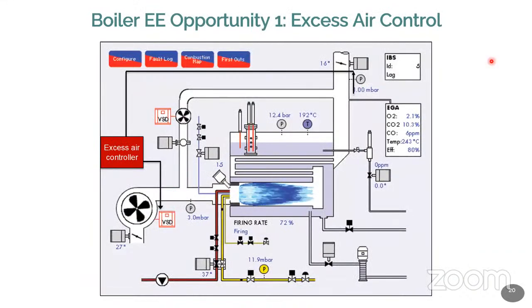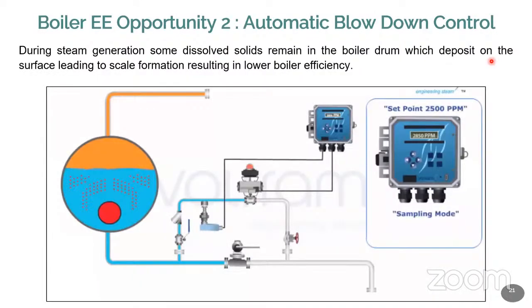Okay, so this will show the way in which the system is working, with monitoring of the flue gas system and excess air control system, where you require boiler operation of the entire system. Then you can have an automatic TDS level monitoring system, normally available, but most of the small boilers are not using it. They monitor manually and blow down the system. If they are not monitoring, they will blow down every shift. That is a thumb rule they are normally using.